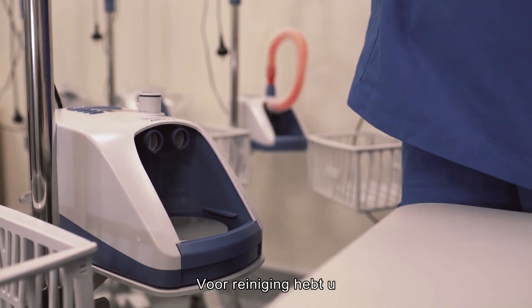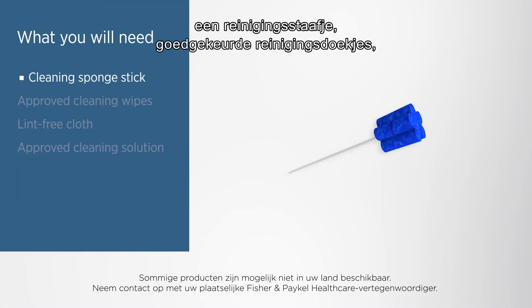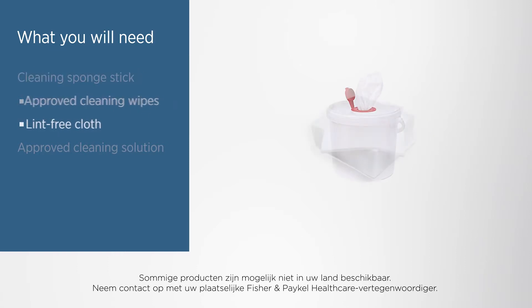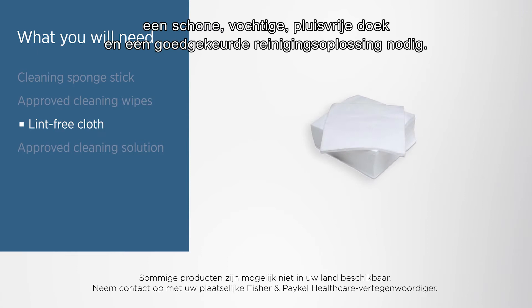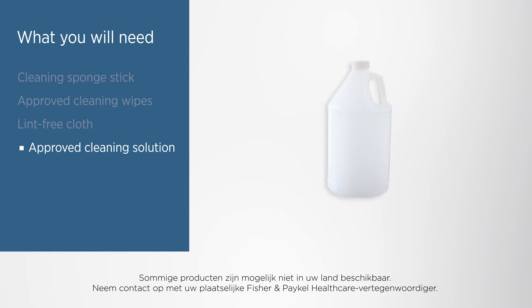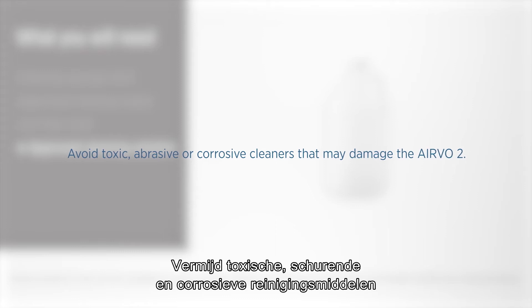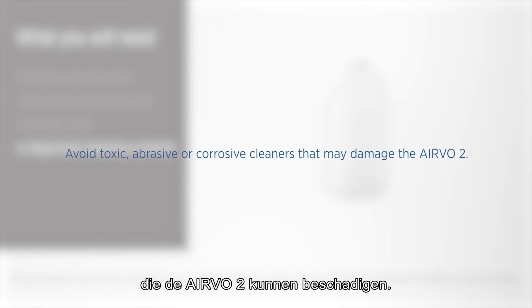For cleaning you will need a cleaning sponge stick, approved cleaning wipes, a clean damp lint-free cloth and an approved cleaning solution. Follow the manufacturer's instructions when using any cleaning solution, diluting it if necessary before use. Avoid toxic, abrasive or corrosive cleaners that may damage the AIRVO 2.